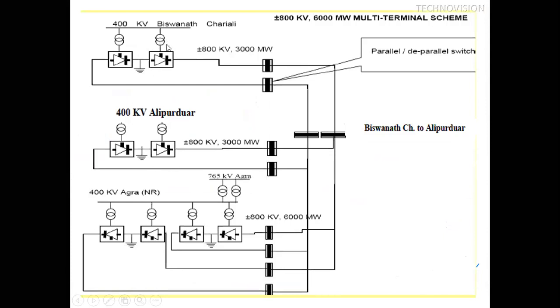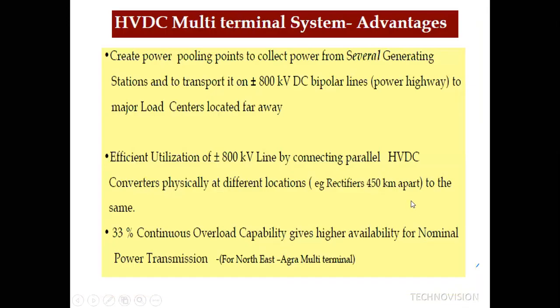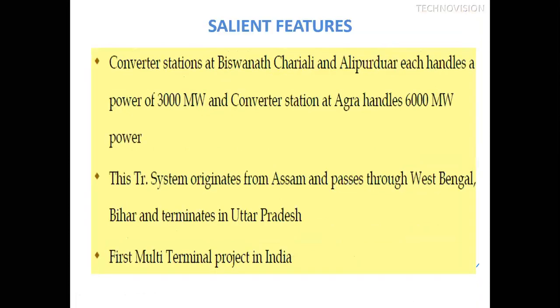But the speciality of an HVDC link is that any rectifier can act as an inverter, and an inverter can act as a rectifier. That is the speciality of the multi-terminal or any HVDC link, we can say. So these are some of the features of parallel operation of HVDC. There are benefits when we operate the system in a multi-terminal way.